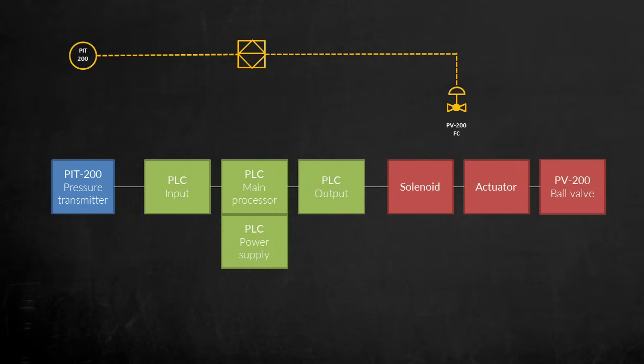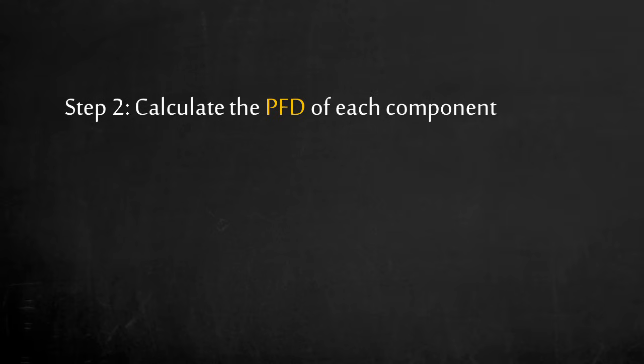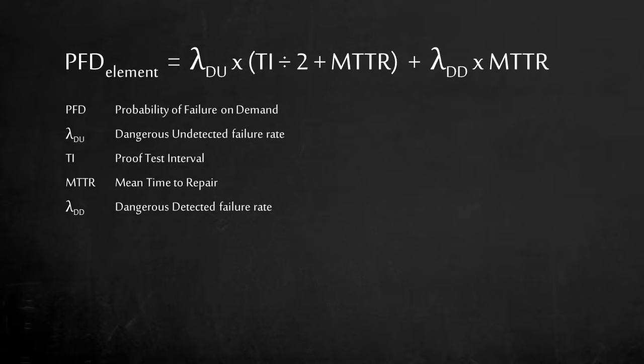We can break down this SIF into the pressure transmitter, programmable logic controller, and final element. Step 2. To determine the reliability of our safety instrumented function, we need to calculate the PFD of each component. With a simple equation, the probability of failure on demand of each element can be determined.